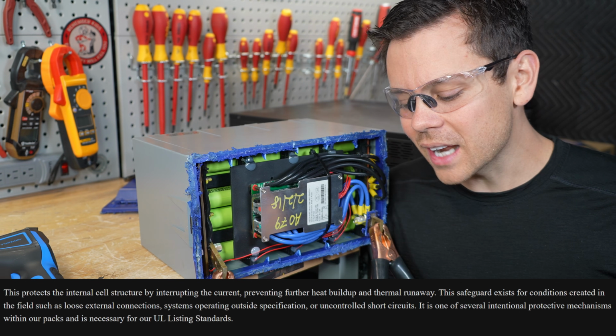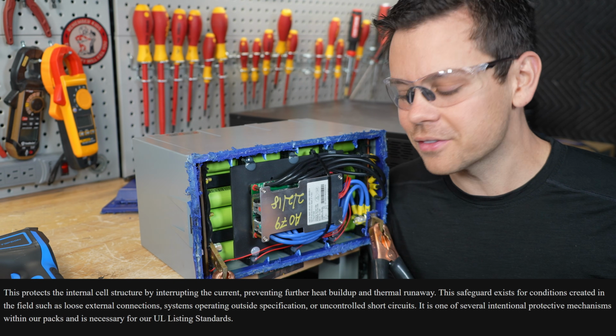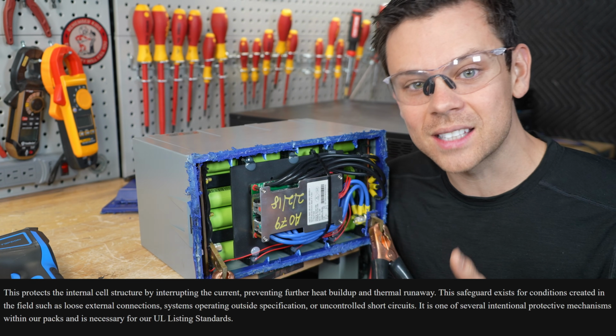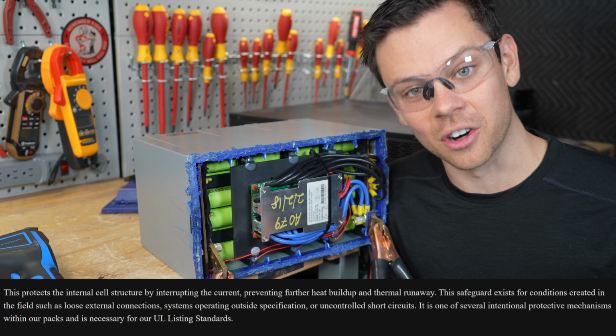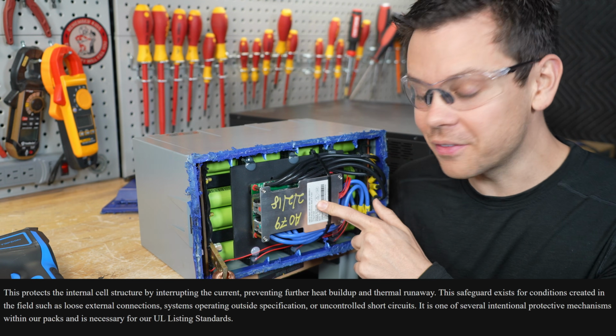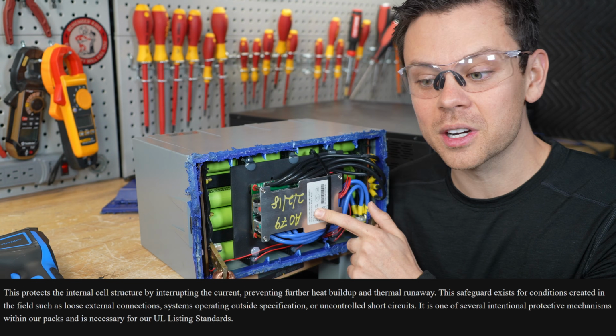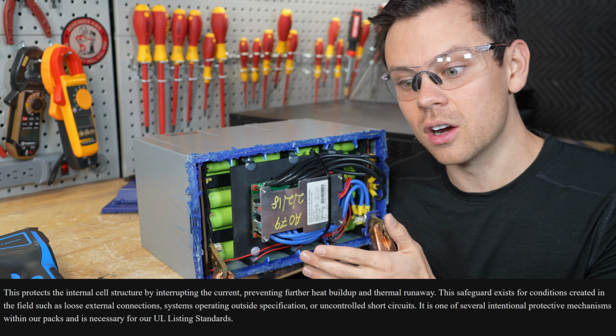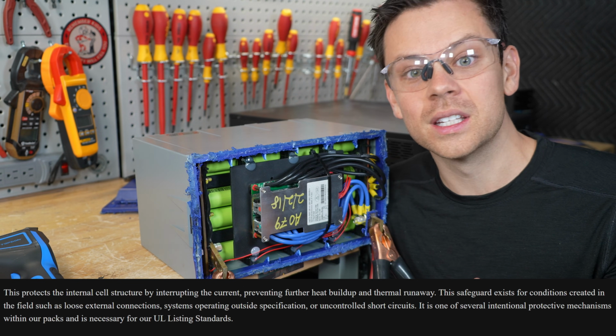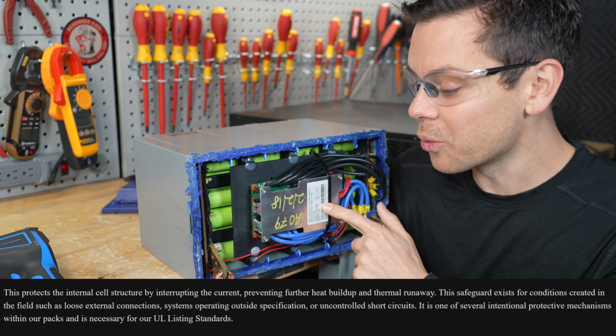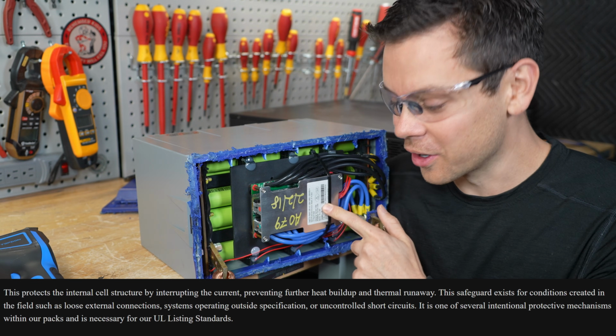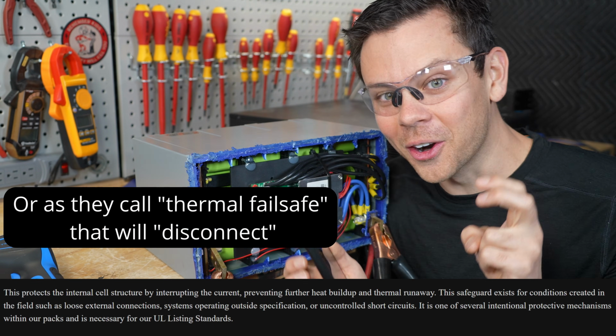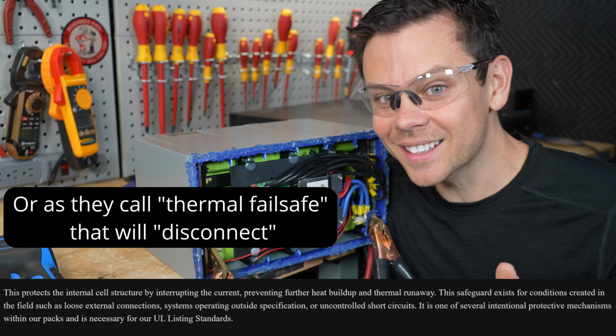Next, systems operating outside specification. Again, add a fuse. Also, the BMS has safety features, including overcurrent protection. Now, if there was a BMS failure and this couldn't disconnect and there was a shorted MOSFET, then sure, I could say, uh-oh, this was probably abused with an inductive load, but it's not. Everything works perfectly. What does not work is this. The overcurrent protection device is not disconnecting anything.